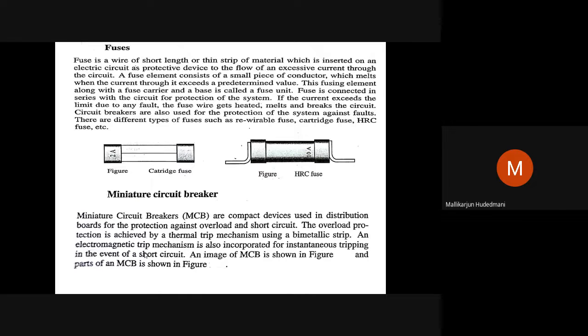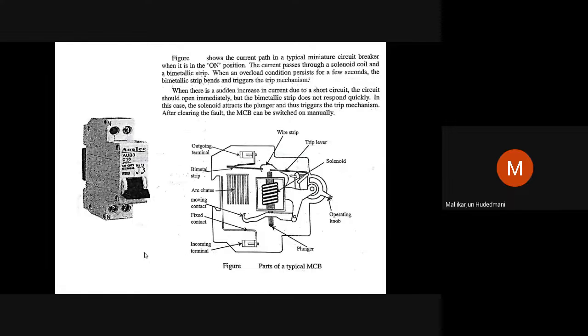Hence the name miniature circuit breaker, which works on the principle of current flowing through a bimetal thermal strip. When the thermal strip heats up due to the Joule effect, that metal will automatically get deformed. There will be a twist of the thermal strip. That twisting mechanism, due to heating up of the bimetal strip, will make the mechanical assembly operate and isolate the circuit from the power supply. That is the principle of working of a circuit breaker. That was what I showed you in the diagram.